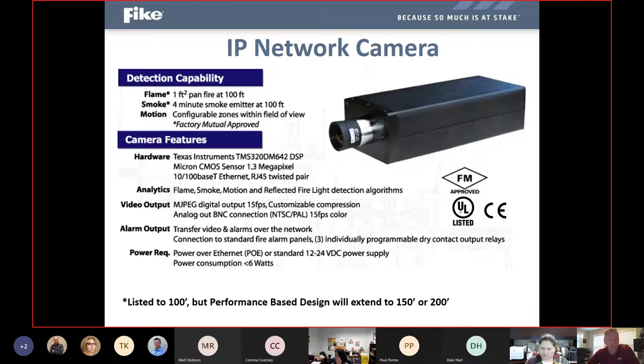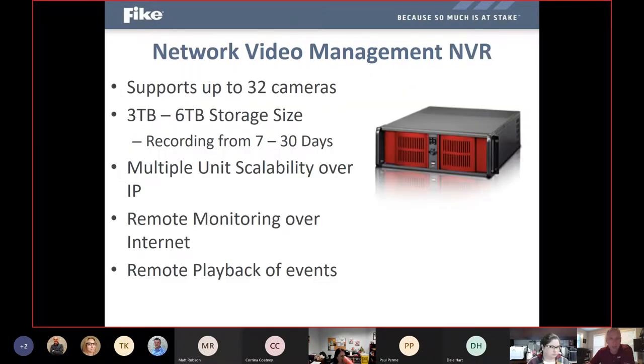And each camera is listed out to 100 feet, but under our performance-based design guidelines, which is what the codes recommend and require for these systems, we can extend that out to 150 to 200 feet with one camera at a very wide field of view to know that anything that's basically in its field of vision is going to be detected in a timely manner in terms of either smoke or flame. And these cameras will go right back to a video management system.